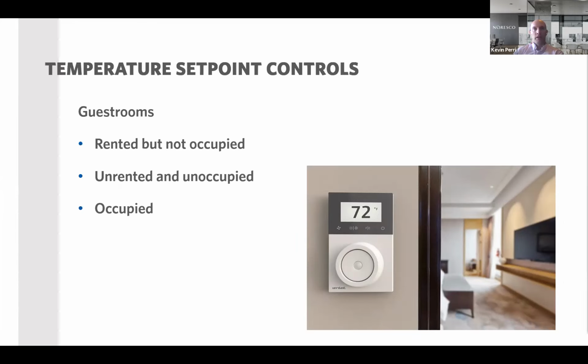different categories. If the space is rented but not occupied, it needs to raise or lower the set point automatically by at least 4 degrees 30 minutes after it becomes unoccupied. So basically, it's rented out, but nobody's actually in the space. They rented it out for 3 days. Well, we don't need the HVAC system on 24/7 for those 3 days. So 30 minutes after they leave, it's going to go into a temporary unoccupied setback. And that needs to be at least 4 degrees.